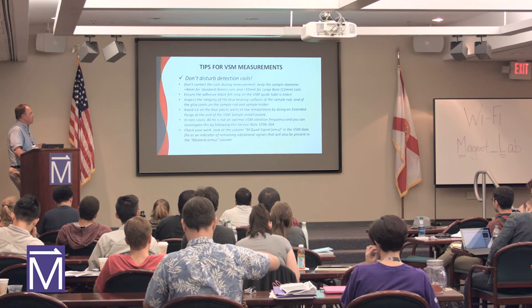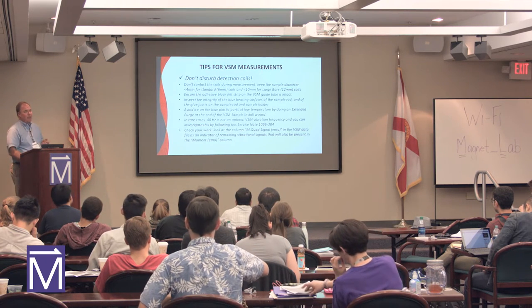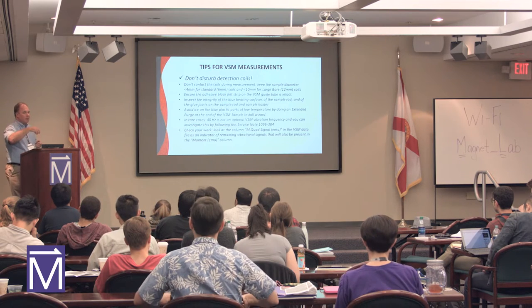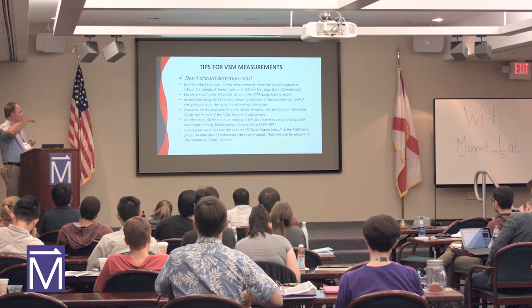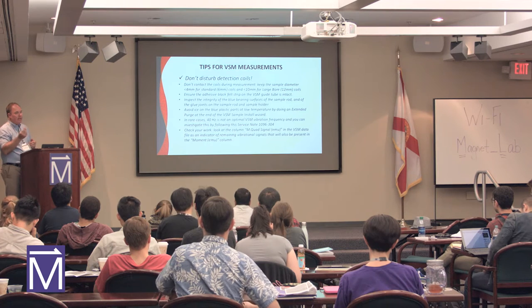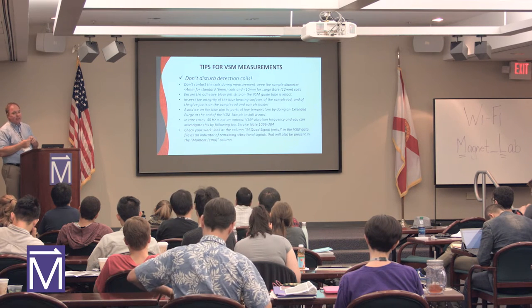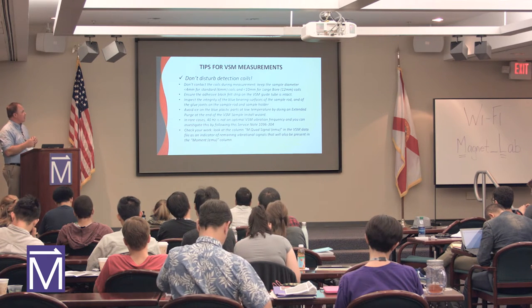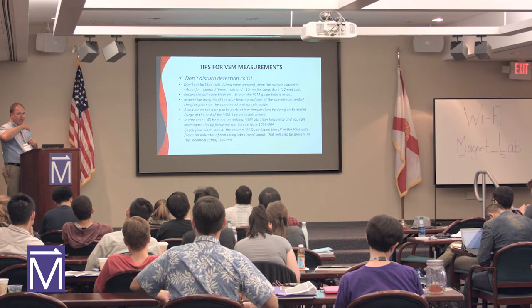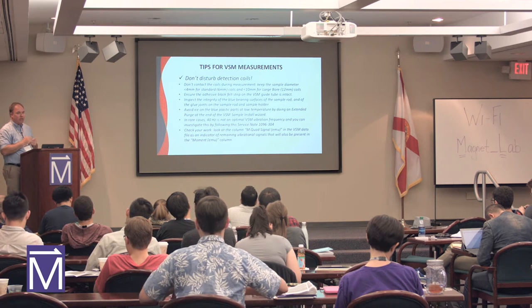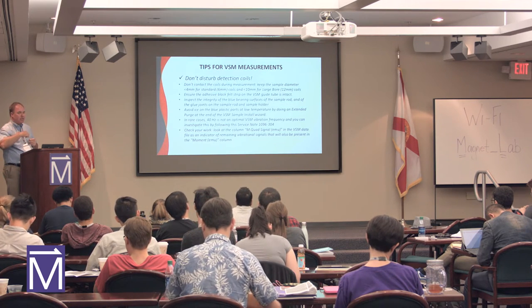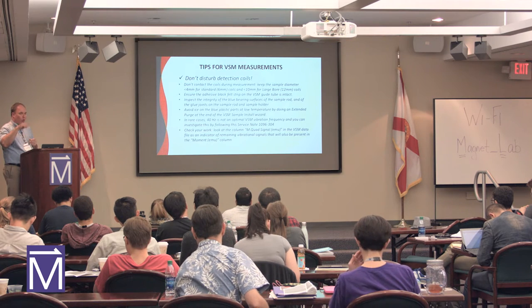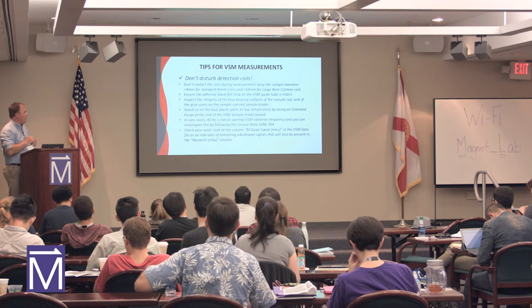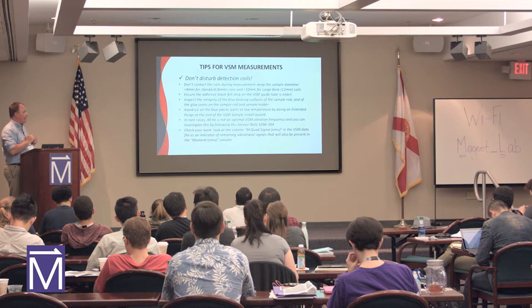So don't disturb the pickup coils. So the coils fit in the bottom of the instrument. If you have a situation where the coils are moving, that's going to add an artifact to your measurement. So you need to make sure the rods and sample rod isn't touching the coil. So if you try to put something too large into the system and if it hits the coil as the sample's moving, it'll bump the coil and give you an artifact.